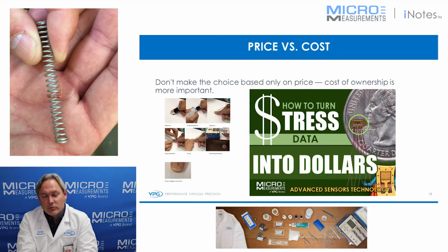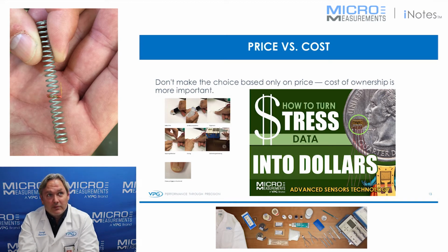And this one kind of goes without saying, really it doesn't need to be said, but don't make the choice based only on price. Cost of ownership is much more important. And what I mean by that is the strain gauges are going to be the least expensive part of your entire measurement. You look at your time, you look at how many labor hours you have invested, you look at the instrumentation, you look at the environmental coatings, the lead wire and all of that, and typically you find the strain gauge is the least expensive part of the entire measurement.